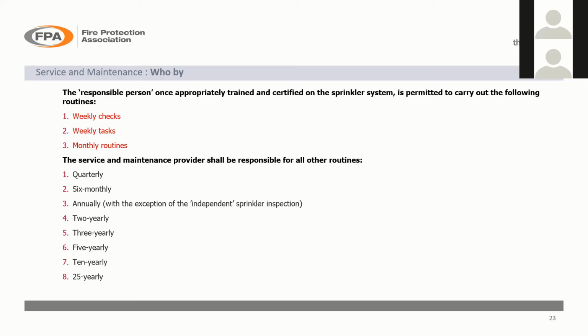You don't want any gaps where the clauses of the standard are not being maintained, because that might invalidate your insurance and also lead to the system itself not being maintained properly. So it's very, very important that you don't just renew your contract. Have a chat with your maintenance contractor, they're the expert. If the maintenance requirements of clause 20 and TB203 are not in the contract, you just need to establish whether they are relevant to your system, and if they are, you should make sure they're actually written into the contract, or you take steps to get them addressed in some way.